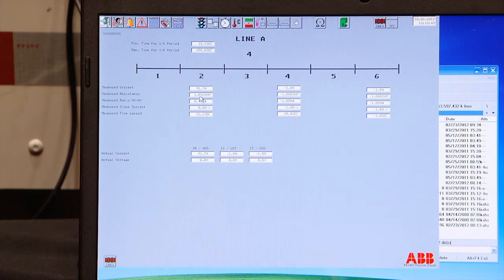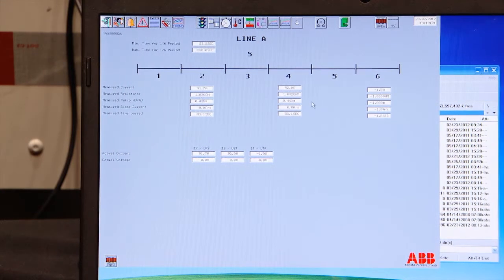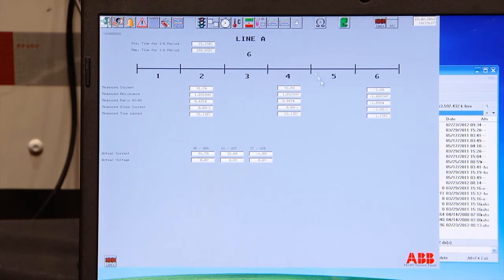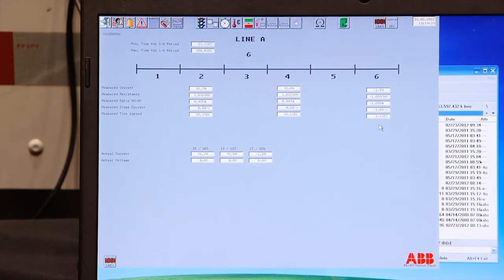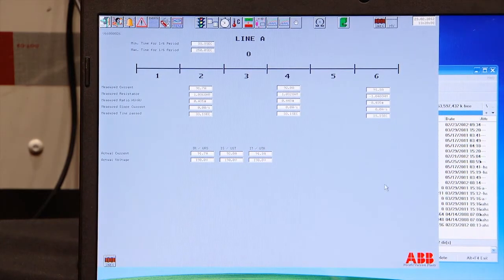So it has increased 3%. Each percent is approximately 3 degrees. We have been heating up 10 degrees. It should not be so much difference between the high voltage and low voltage. Phase number 2 is finished. Running in preparation phase number 5, switching to number 6. Phase number 6 is finished.